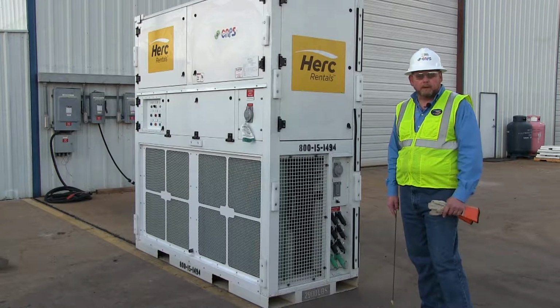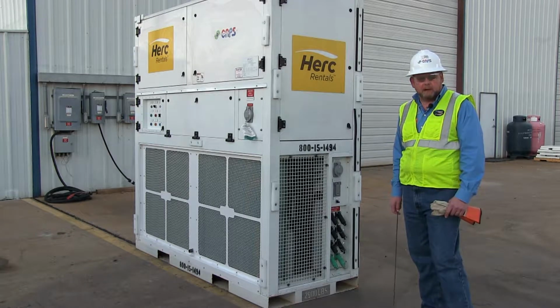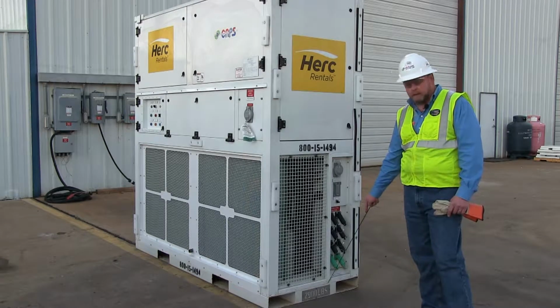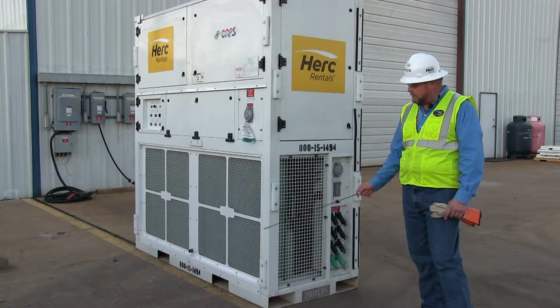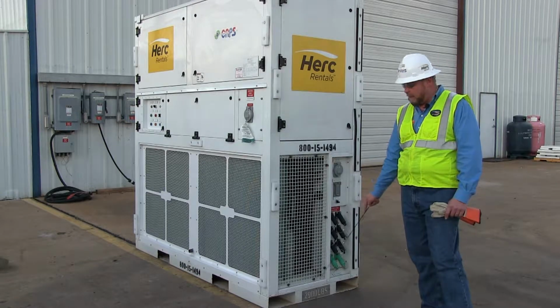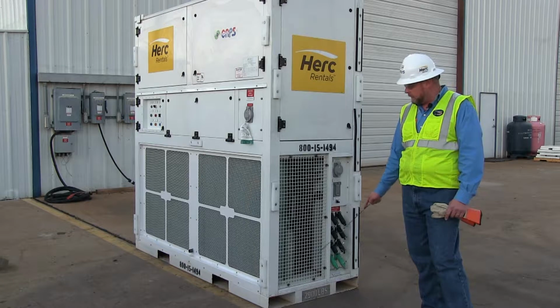Before transporting the unit, the first thing you want to do is verify the unit weight, which is clearly marked here on the bottom of the base. The 20-ton vertical unit has two integrated sets of fork pockets, so it can be forked from the narrow end or the wide end.